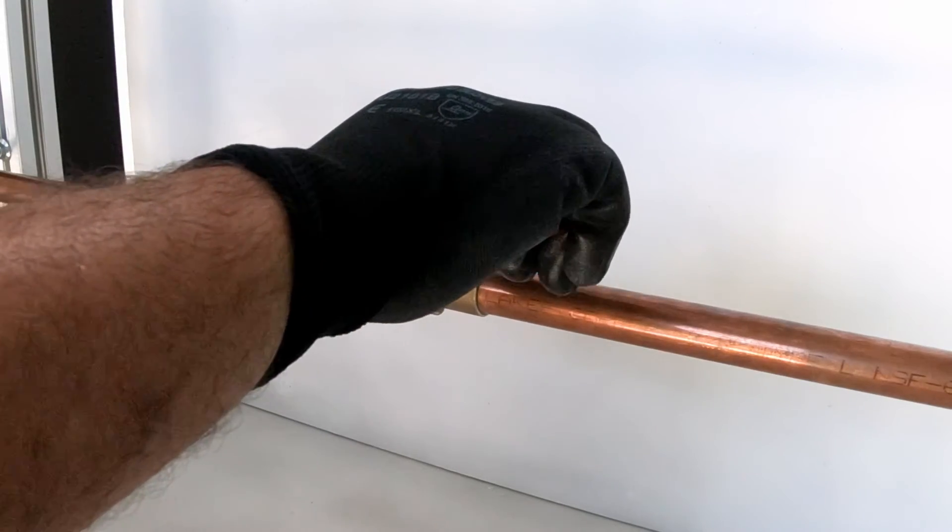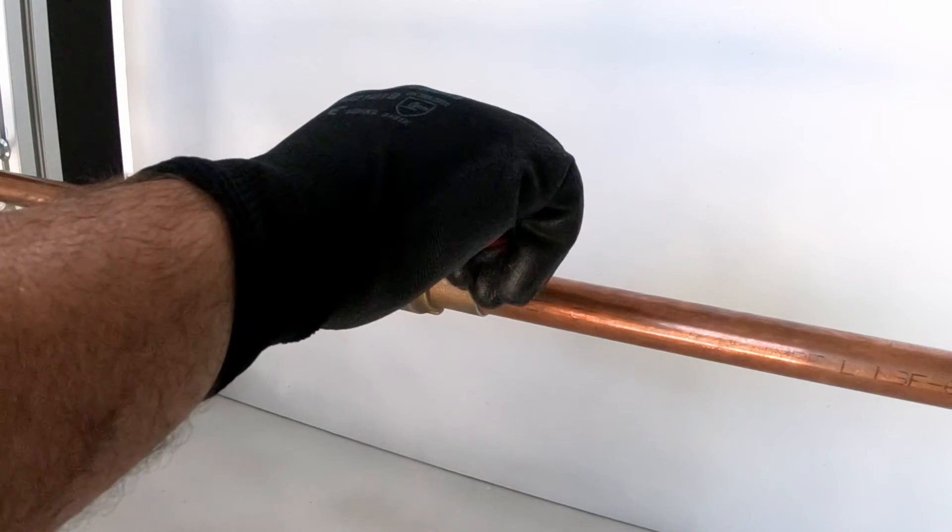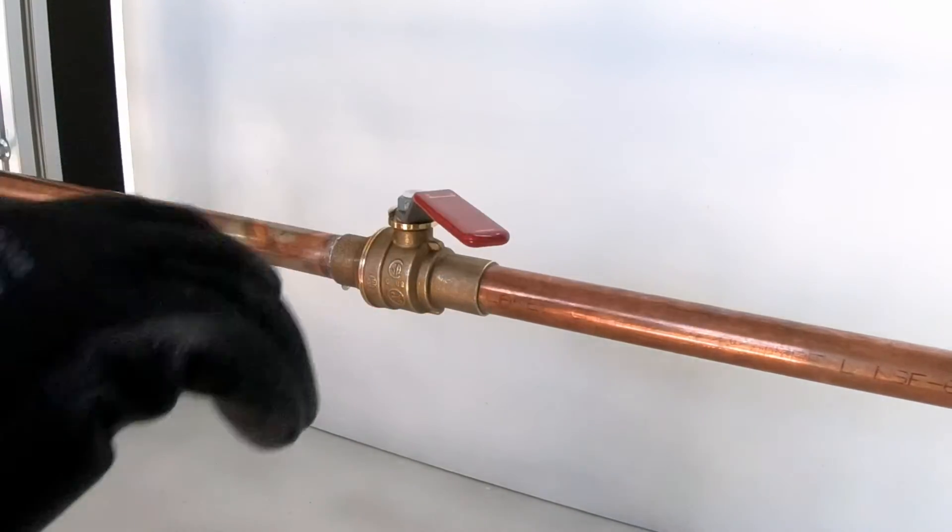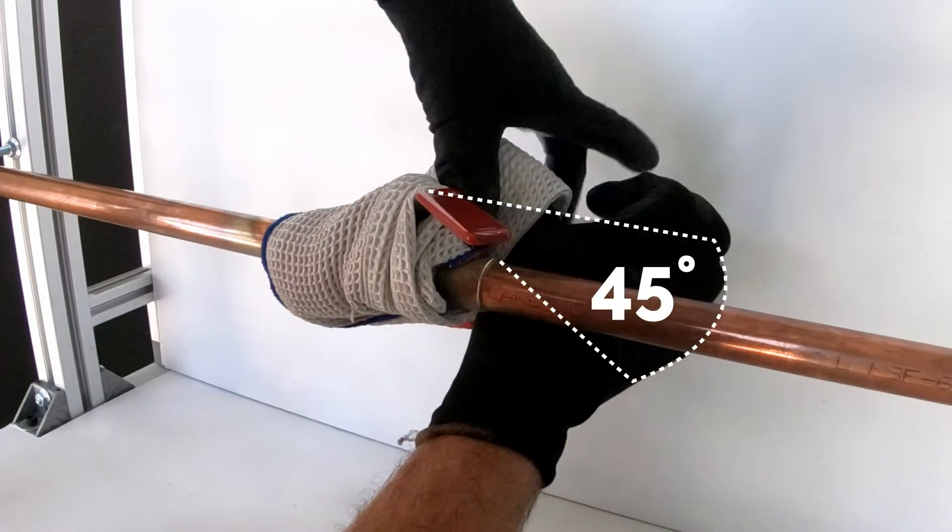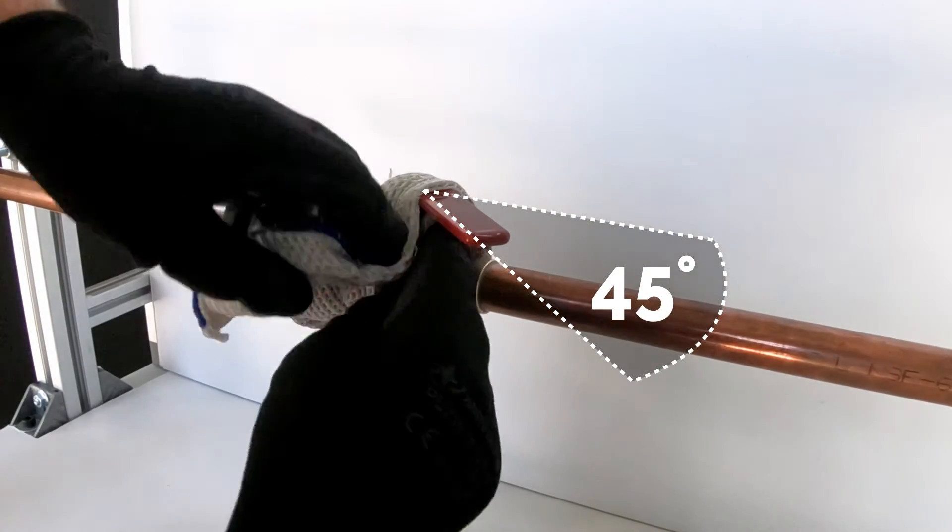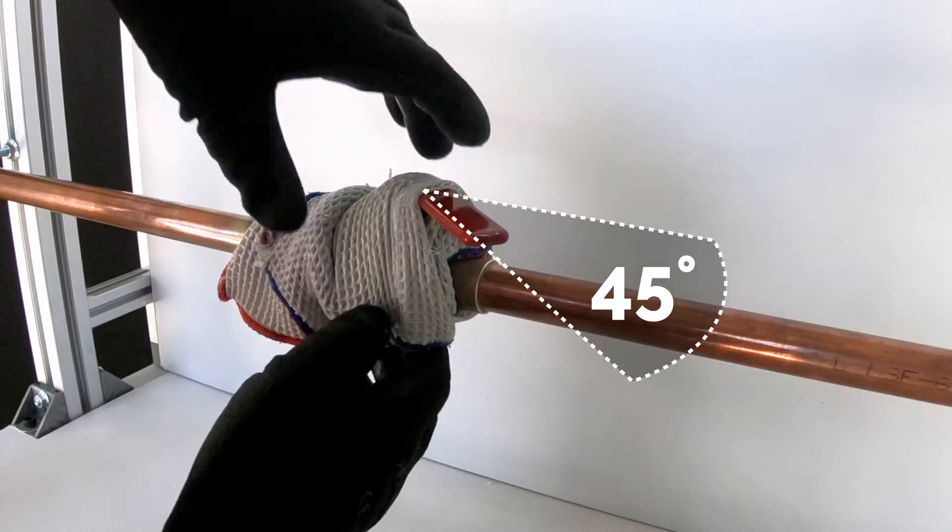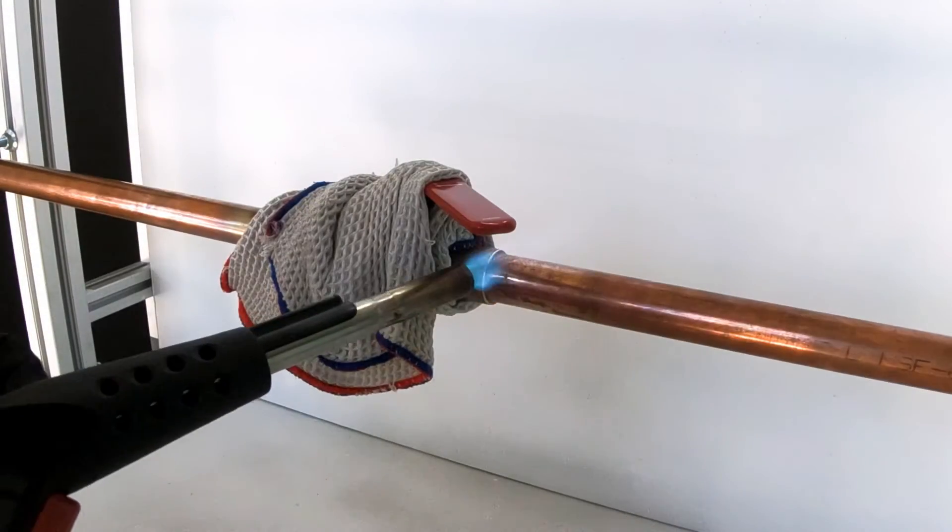Repeat this same process for other end. Before this step, slightly move the handle clear of flame area to avoid heating of vinyl grip, but do not completely close valve. A 45 degree angle is perfect. It's also acceptable to keep the valve in this position for the entire process, provided it doesn't create inconvenience or affect safe handling of the valve.